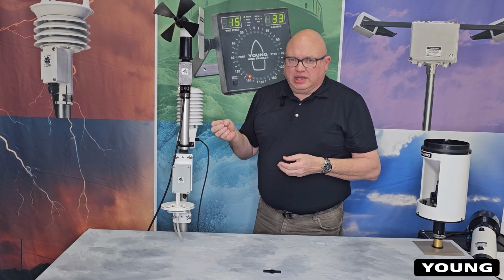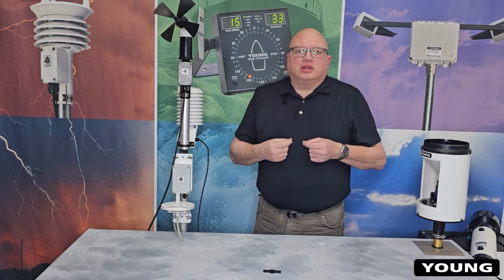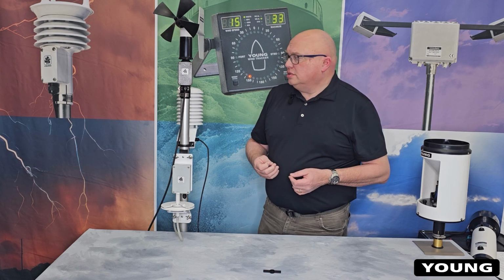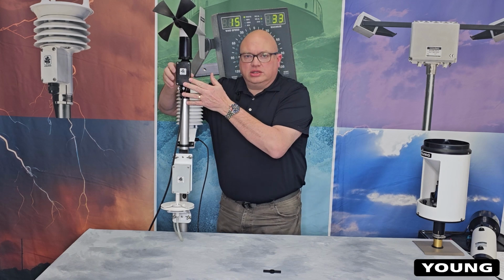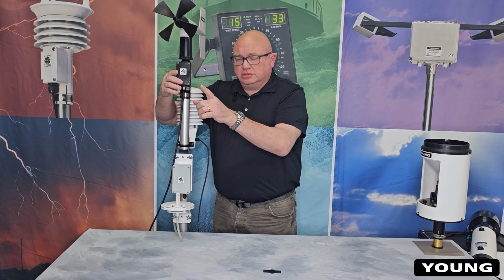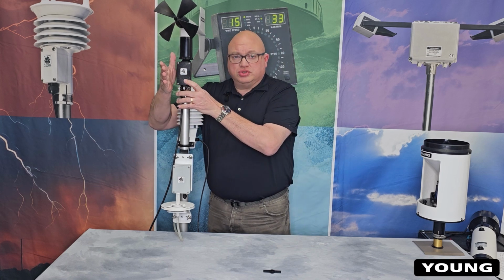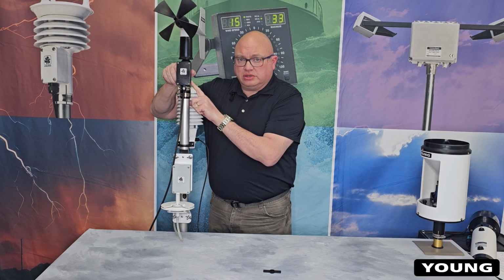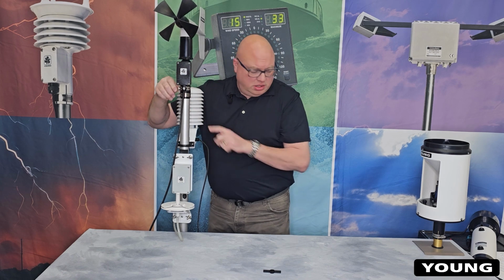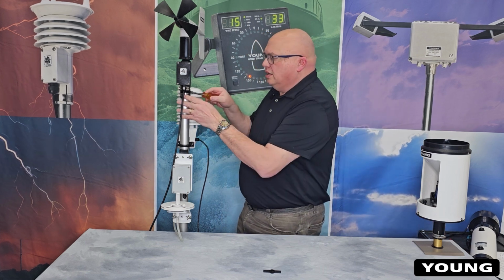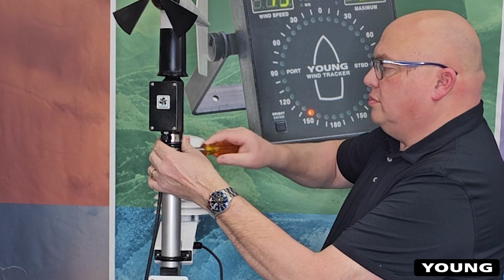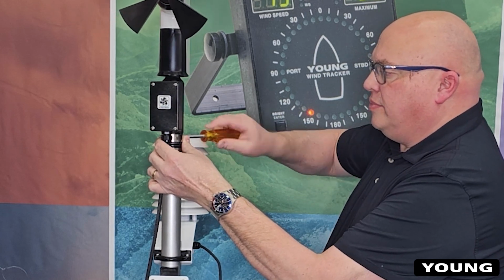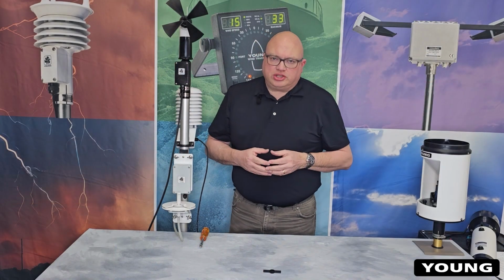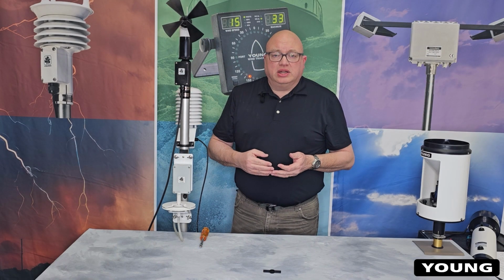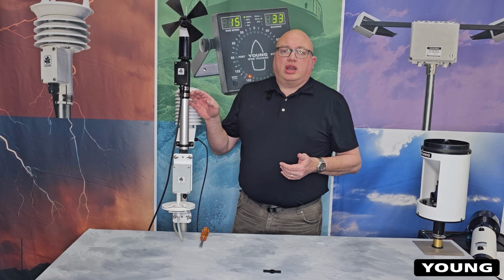Now that you have the wind monitor installed on the mast, comes the most important part. The sensor needs to be aligned properly to give you correct wind direction readings. You'll want to align it so that the junction box is pointed due south. Once you have sighted it due south, make sure that the wind monitor itself is indexed into the orientation ring, and only then tighten down both clamps. The purpose of the orientation ring is so that should you need to remove the wind monitor from the mast for maintenance or calibration, when you're leaving this in place will allow you to reinstall the wind monitor without having to take the time to sight it once again.